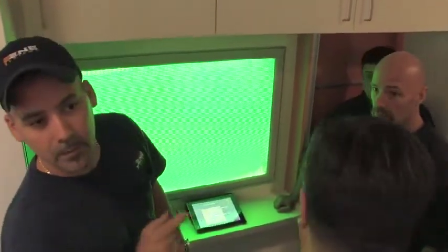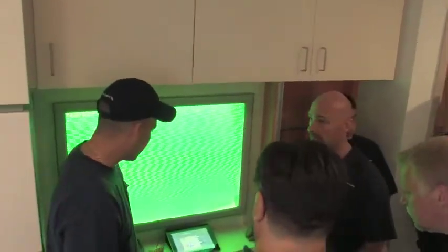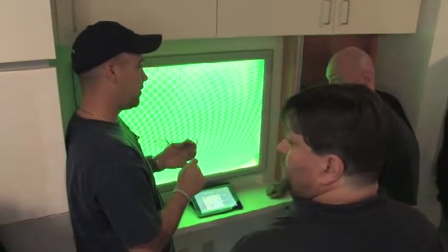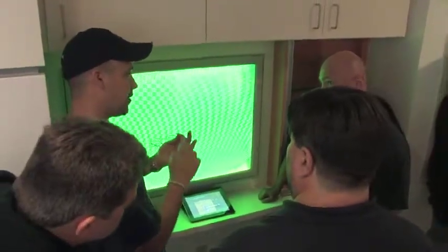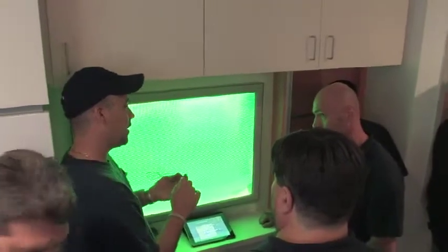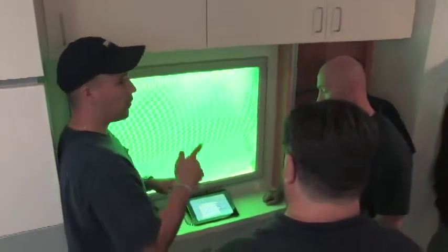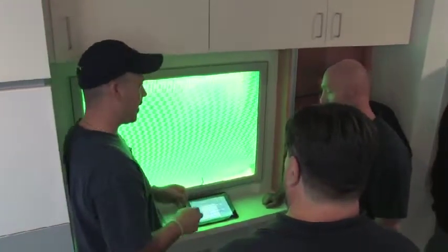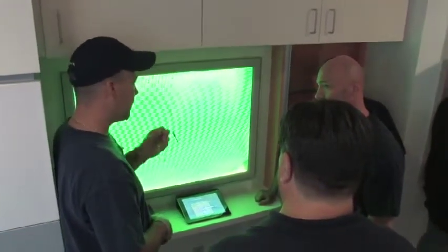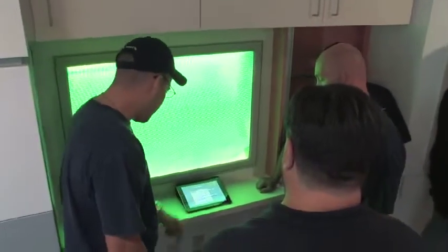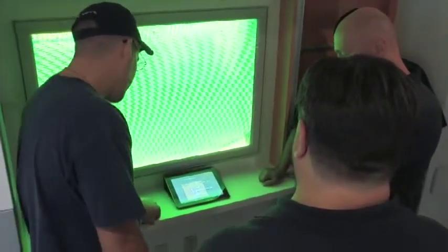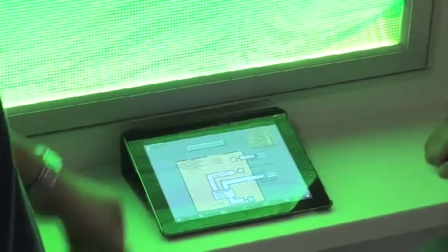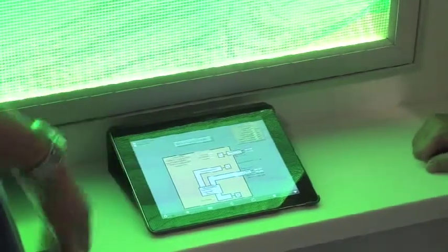I don't have my control screwdriver with me, but there are 3 HT sensors instead of the S3. So there's an S3 sensor that's just the temperature, and then there's a 3 HT that's the temperature and humidity. If you replace that with just a temperature sensor, make sure, because they look exactly the same, you're not going to have some of the readings. You're taking the readings out. So that's going to be gone. When you say gone, will it just be 0 readings there? No, you won't see it at all. It won't read, so that way you'll know you did something wrong.